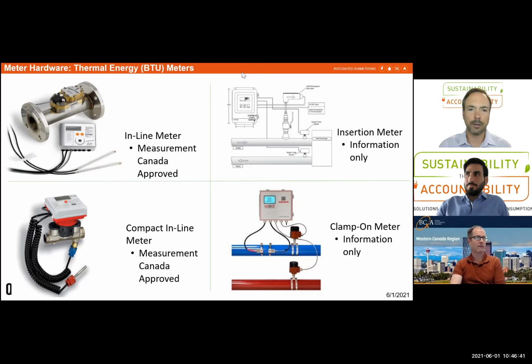Yeah, there was a question here about whether the meter cost was installed or product cost. As a general rule of thumb for the numbers that Peter provided on these meters, you would probably use a percentage of about 60 to 80% of their material costs for the labor cost. So if it's a $5,000 meter, it's probably a $3,000 to $4,000 install. Pete, is that a safe figure you'd agree with? With the exception of clamp-on meters, which typically offer a much lower installation cost as they get installed on the surface of the pipe.